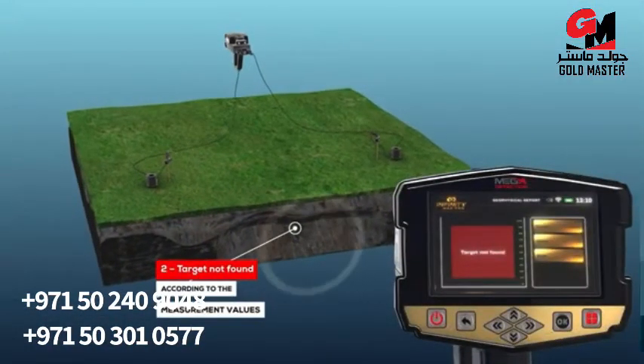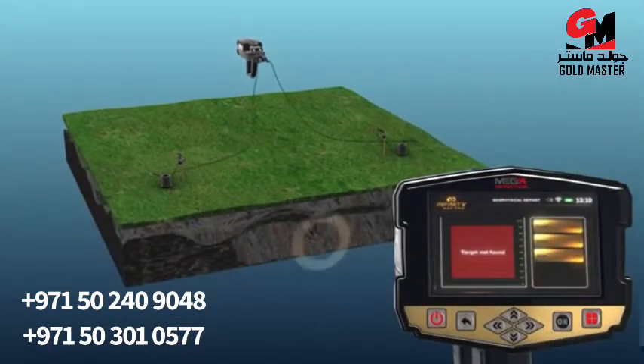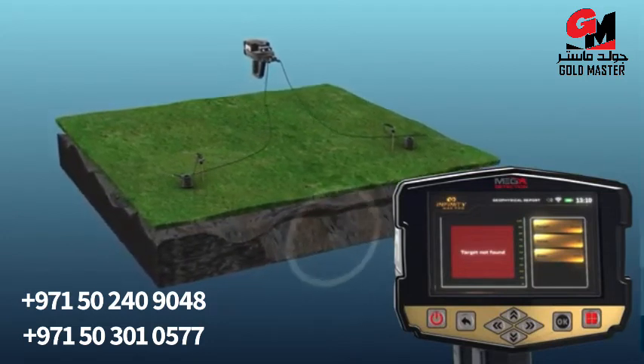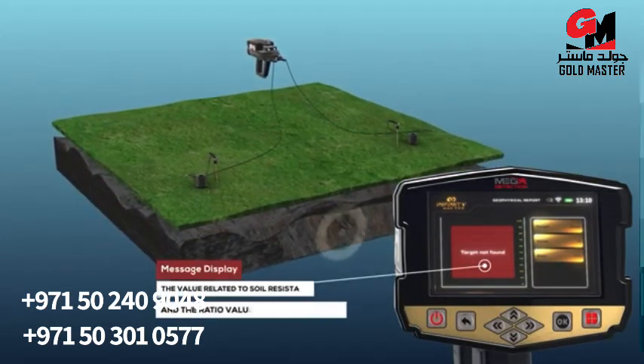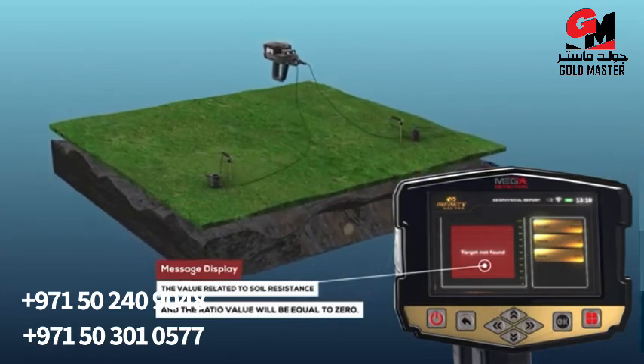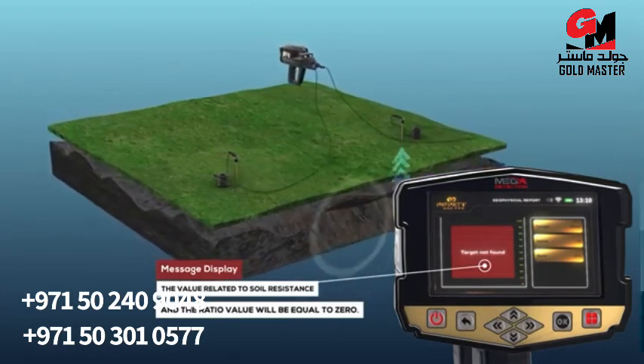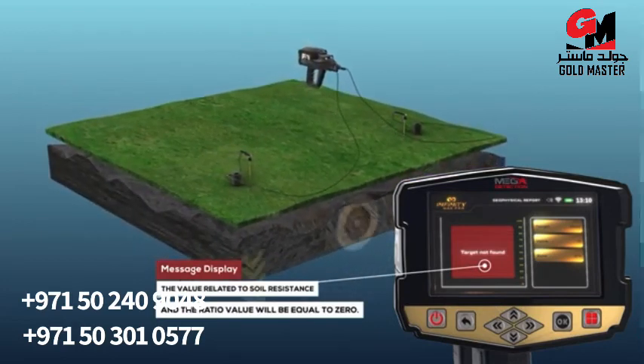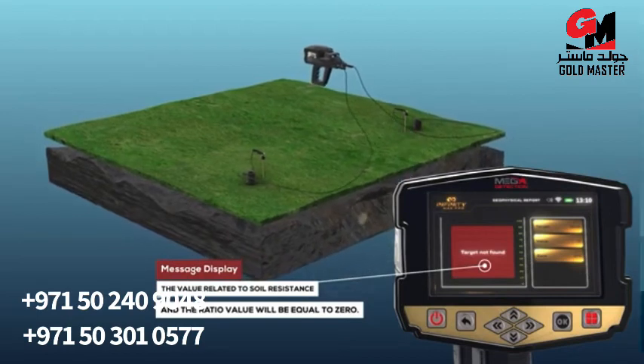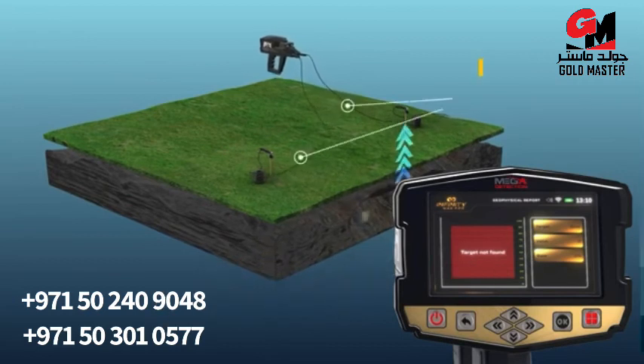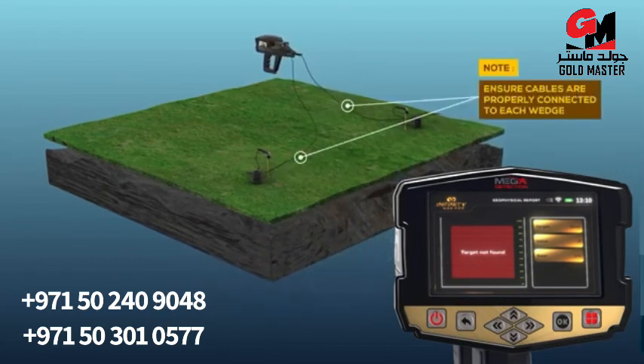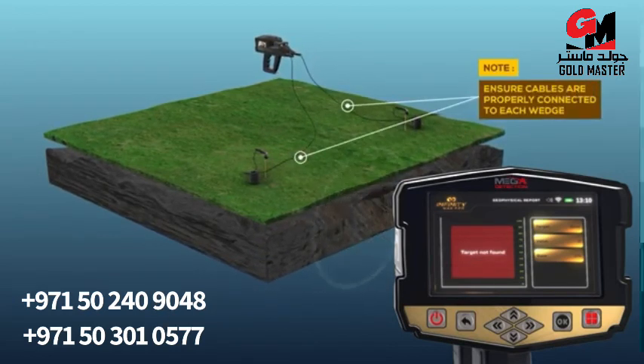Target not found: The ellipsoid curves will not be drawn; instead, a message will be displayed indicating that the target was not found. In this case, the soil resistance value and the ratio value will both equal zero. Note: ensure cables are properly connected to each wedge. If one of the wedges is not connected, a message will be displayed indicating that the target was not found.